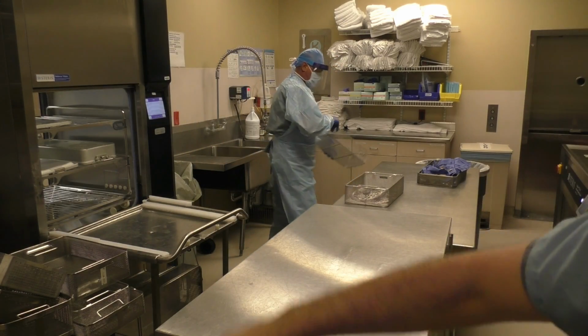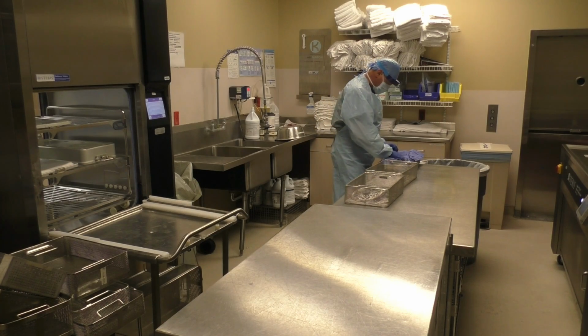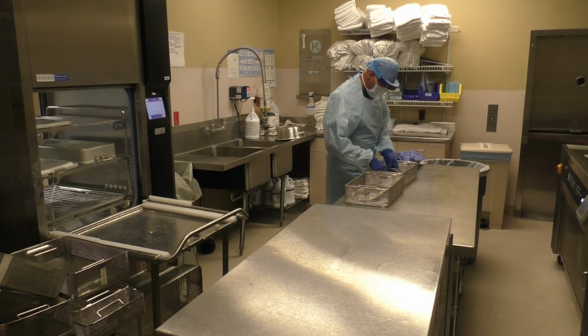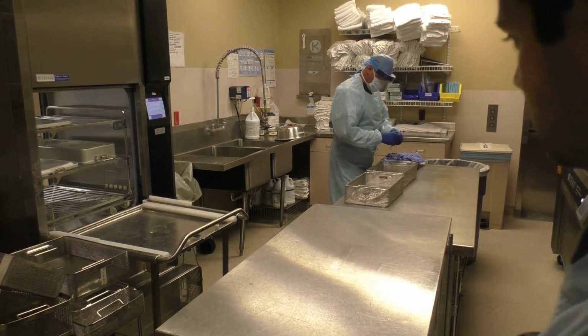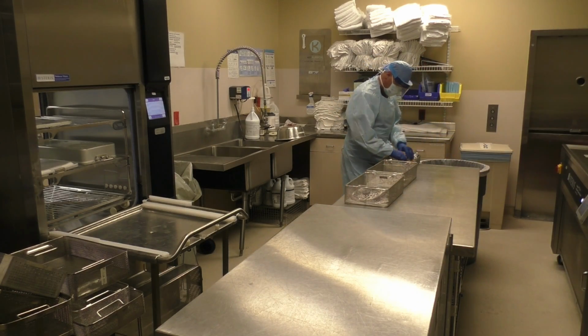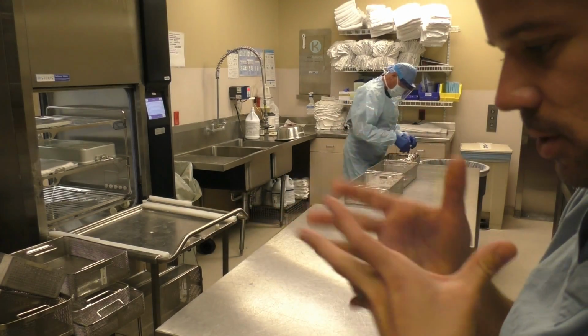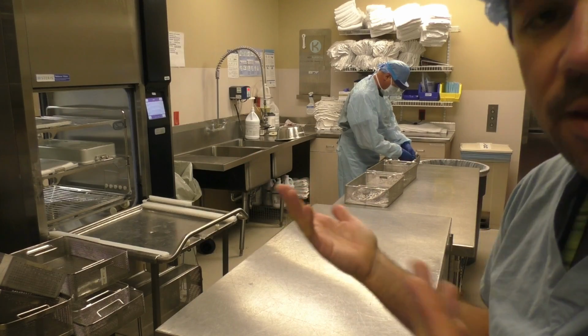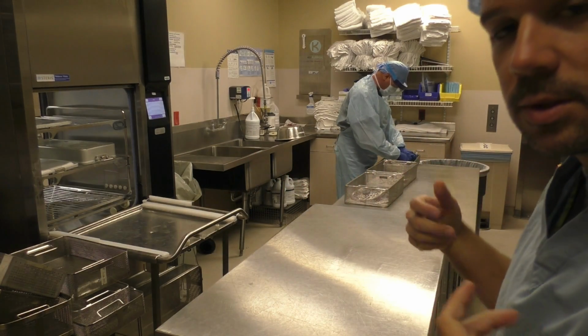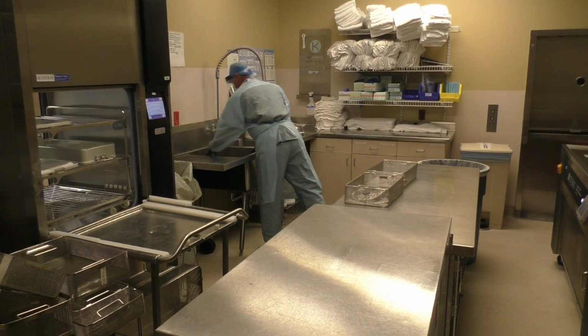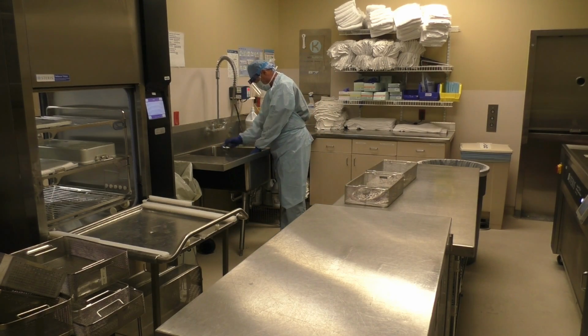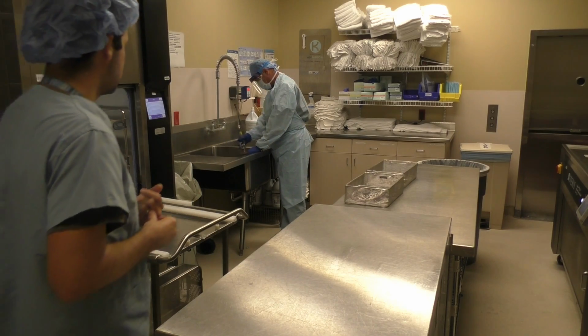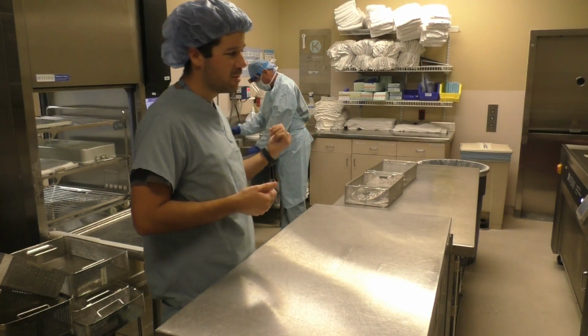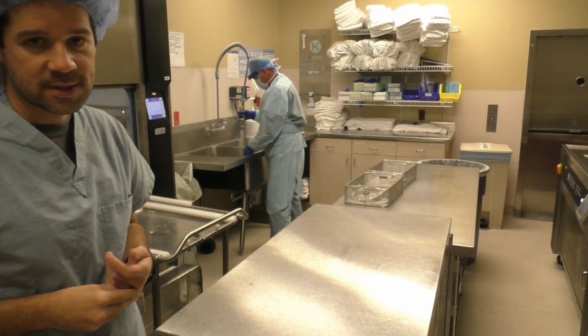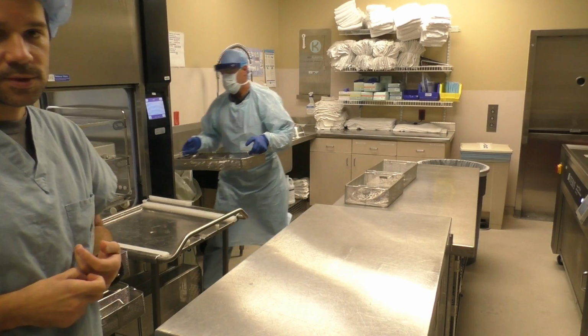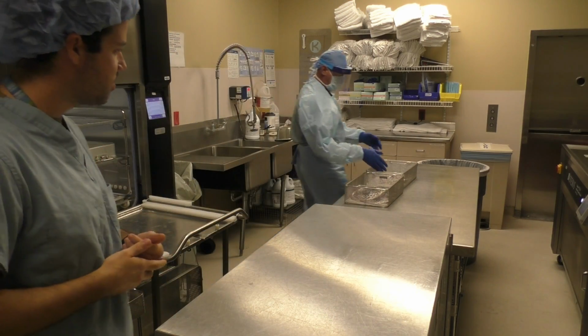So you can see he's putting all of the pans inside the washer. Got all the instruments now, putting them in a separate container, opening all the instruments up. So none of the instruments are closed. When the instruments are closed, obviously nothing is going to get cleaned underneath the teeth and stuff like that. So you got to make sure all of those instruments are opened up. Right into that tub. The general rinsing of the instruments. Get all of that gross contamination off the instruments, and then just popping it in the washer.